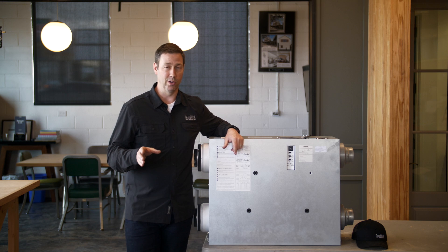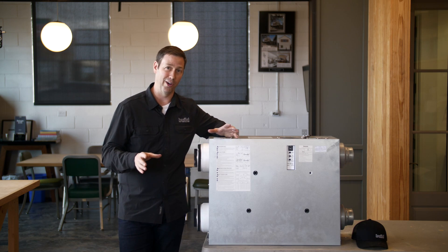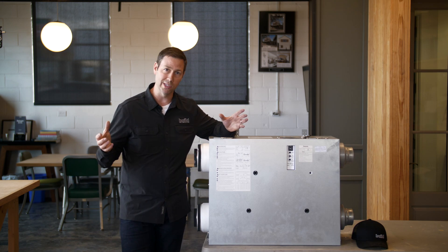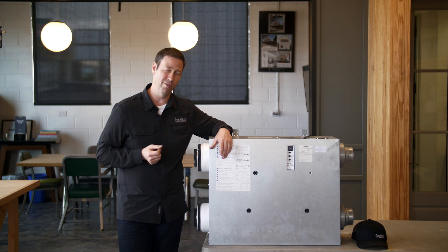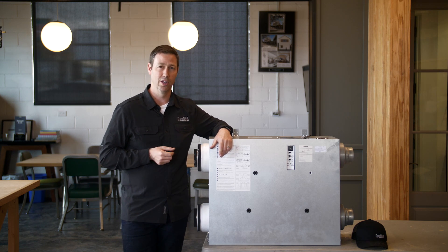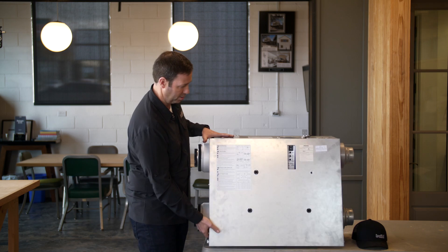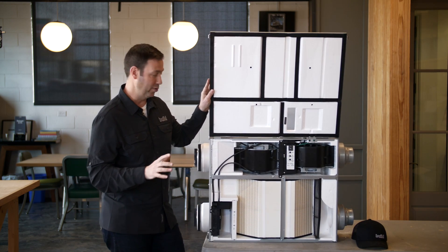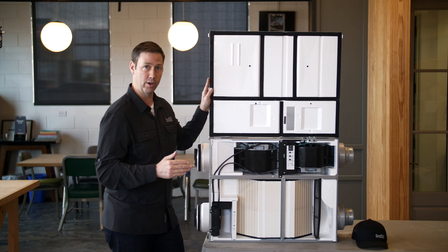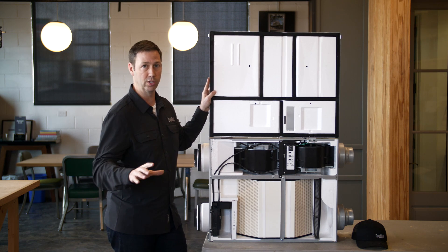Now the problem with these units though, that I've seen out there, is there's a lot of myths. There's a lot of misunderstanding about what these units do. I hear people saying, my ERV is going to dehumidify my house. There is nothing inside here that's dehumidifying. All it's doing is moving the moisture from one airstream to another. So there's no dehumidification.